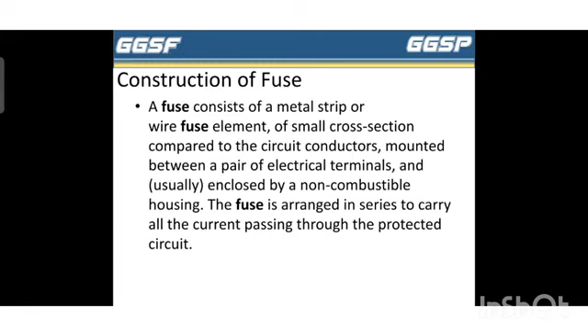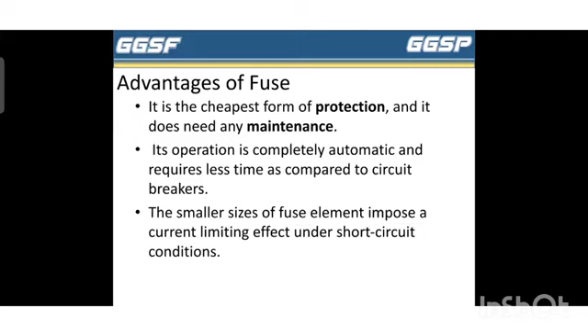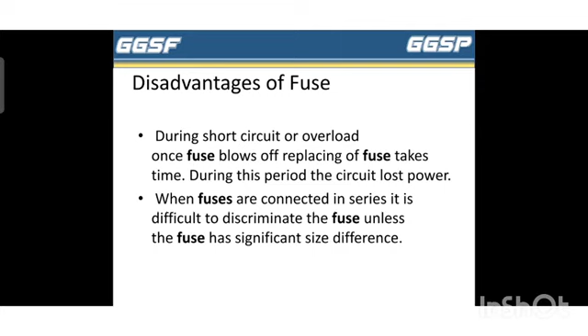Advantages of fuse. It is the cheapest form of protection and it does not need any maintenance. Its operation is completely automatic and requires less time as compared to a circuit breaker. The smaller size of the fuse element improves the current limiting effect under short circuit conditions. Disadvantages of fuse. During short circuit or overload, once a fuse blows, replacing it takes time, and during this period the circuit remains off. When fuses are connected in series, it is difficult to discriminate between the fuses unless they have significant size difference.